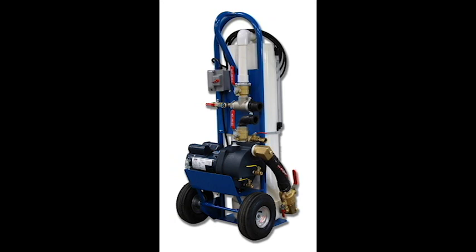Power flushing is a technique that can be utilized to help purge air from a ground loop when the standard flushing procedure does not eliminate all air from the loop. For most systems, power flushing is not necessary. This procedure utilizes the flush cart pump and municipal water pressure together to provide maximum system pressure to compress and purge air pockets. In effect, the flush cart pump is in series with the municipal water pressure.